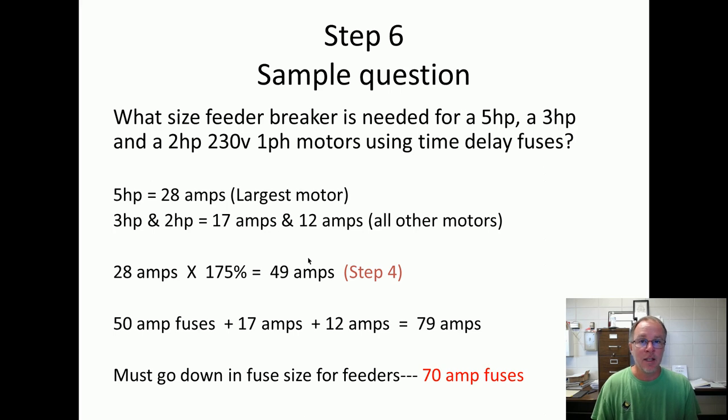Step 3 is easy because whatever the full load current is, multiply it times 125%. You may have to go find a wire size every once in a while. Step 4, there's a chart that tells you the multiplier. And for step 5 and 6, you do step 3 and 4 and then add other motors. So these ain't hard. Don't let these intimidate you because they're easy.